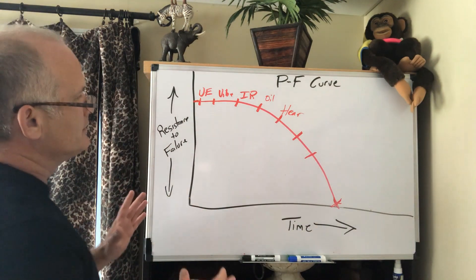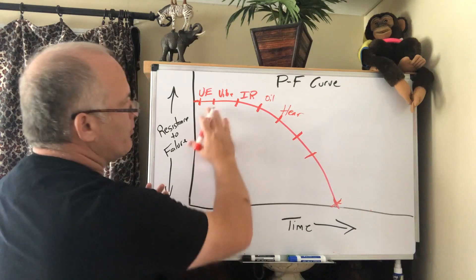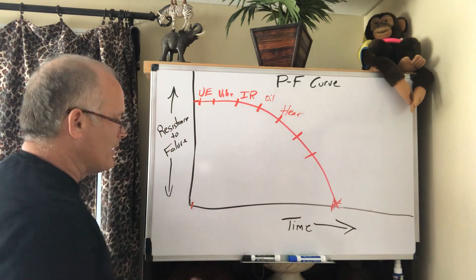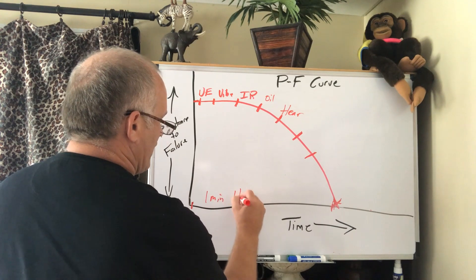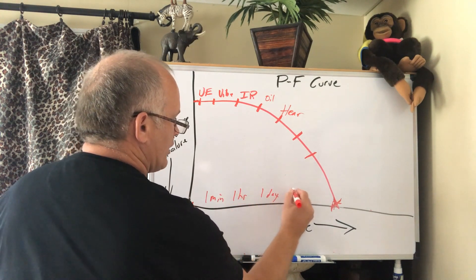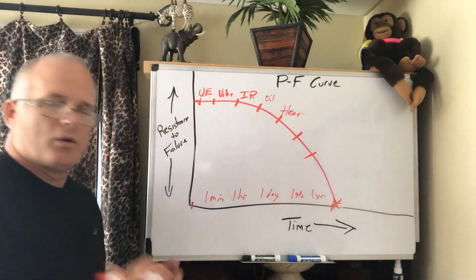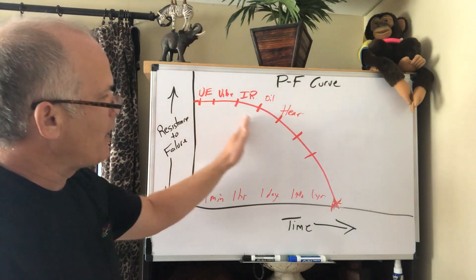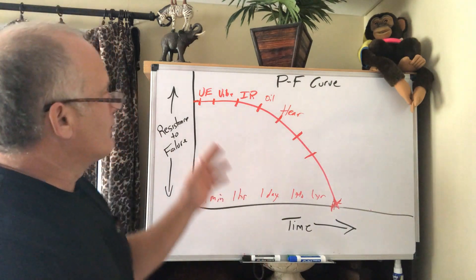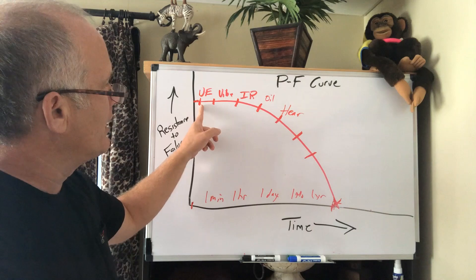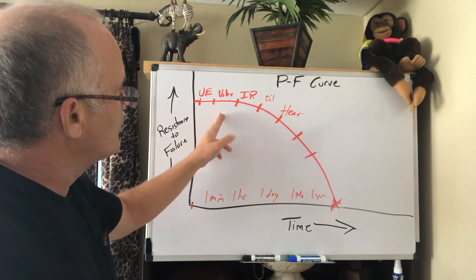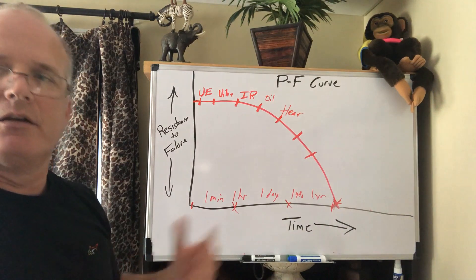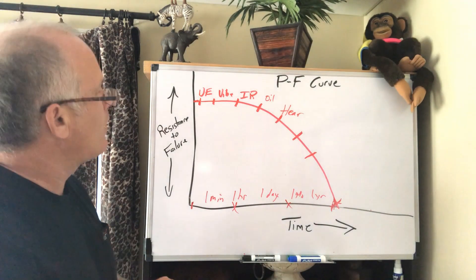The problem with this curve is that it looks simple to see the progression and the time from early detection to the end. But the reality is this interval could be one minute, one hour, one day, one month, or even one year — you really don't know. People try to maximize that window, tracking a UE find all the way through to failure, but that's a dangerous game. The best approach is: you find something on UE, keep monitoring it, and if it gets a little worse, look for windows of planned outages, go in, and change out that bearing early.